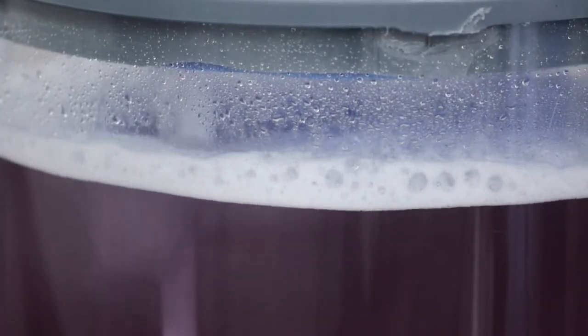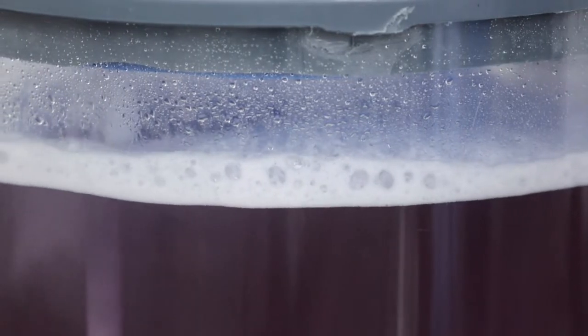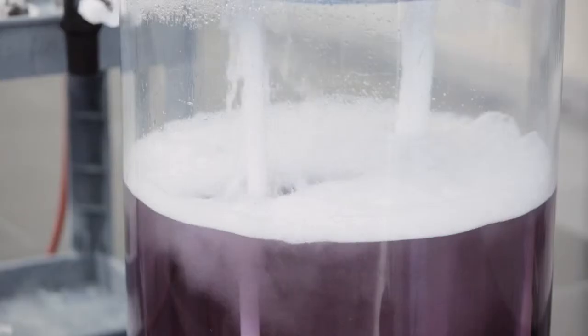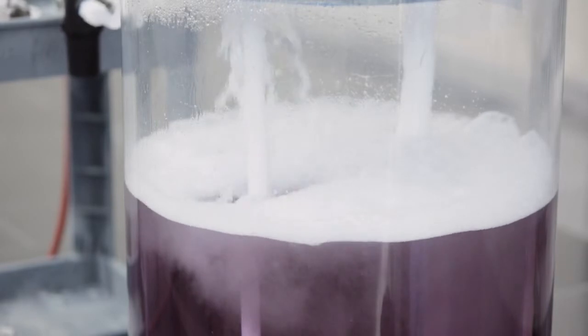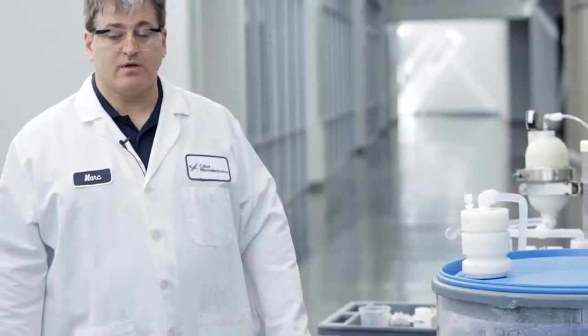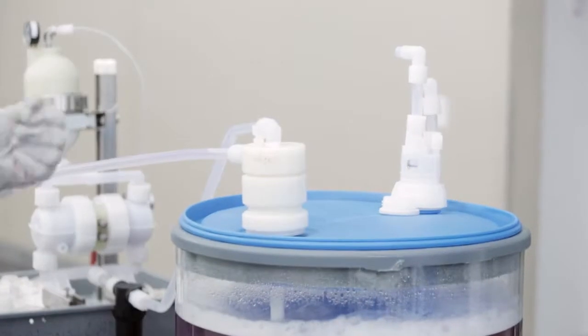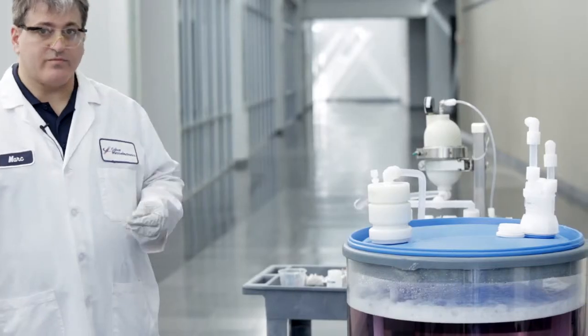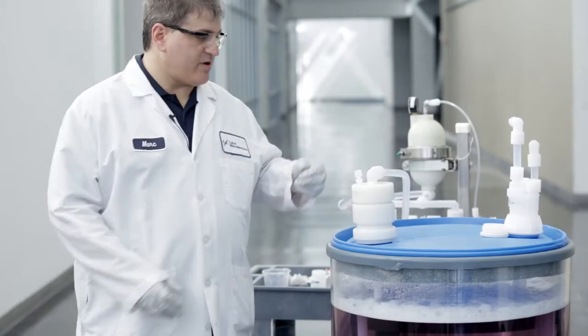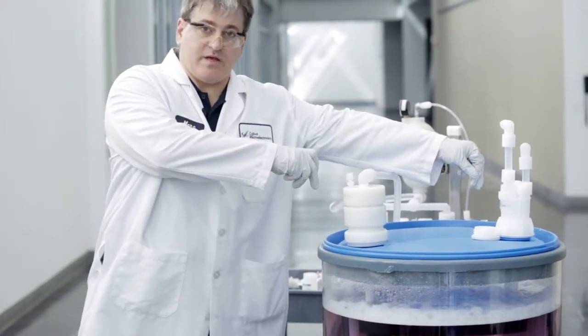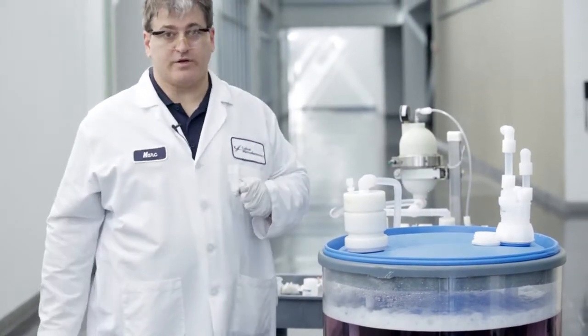So you can see, even at a relatively short drop of maybe 4 or 5 inches, we've already generated a pretty generous amount of foam. As the level in the tank drops, that fall height increases and the amount of foam goes up significantly. For that reason, we uniformly recommend that you use separate feed and return dispense heads and dip tubes for all foaming slurries.